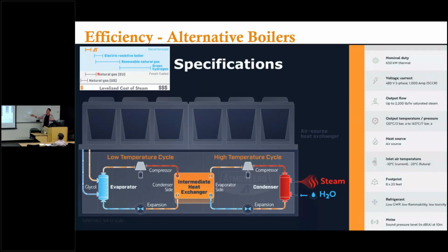But if you put in an electrode boiler, which uses electric resistance, especially at a large industrial site, you're looking at a draw of 10 megawatts. With electrode boilers, you're looking at increasing that draw up to 22 megawatts if you switch out your boilers. Looking at what your transformers bring into the site, you might have a maximum capacity of 11 megawatts per feed. With 2 feeds, that's 22 megawatts. You don't want to max out your site because then you have no room for growth in that industry.